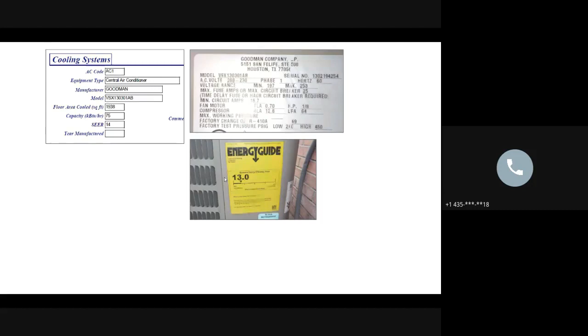Any HVAC guys out there? The capacity is probably wrong. Why would you say that? Capacity—what's your heartburn over the capacity? It looks like from the model number it's a 2.5 ton, and they've got it entered as 75,000 BTUs. So if it's a 2.5 ton, how much capacity in kBTUs would that be?